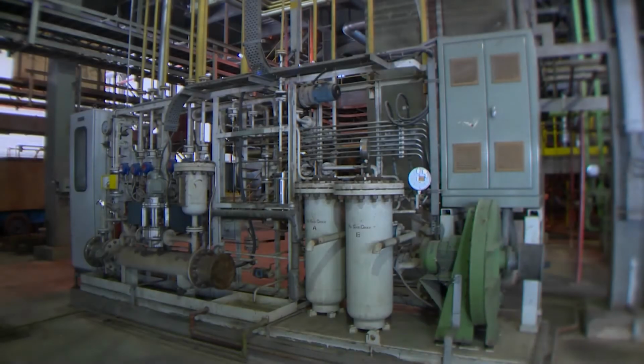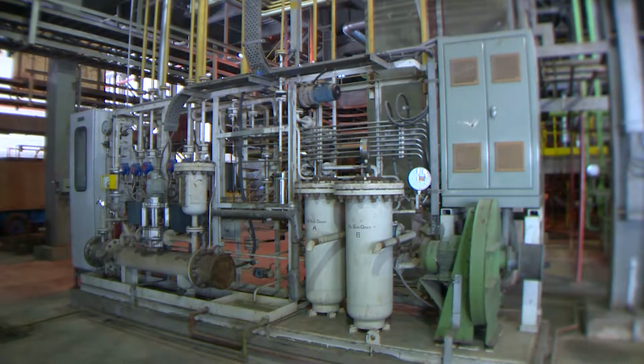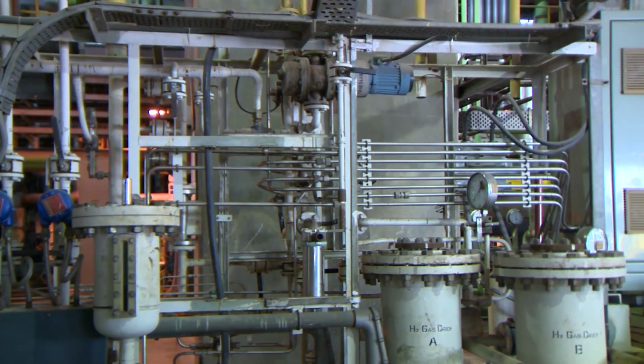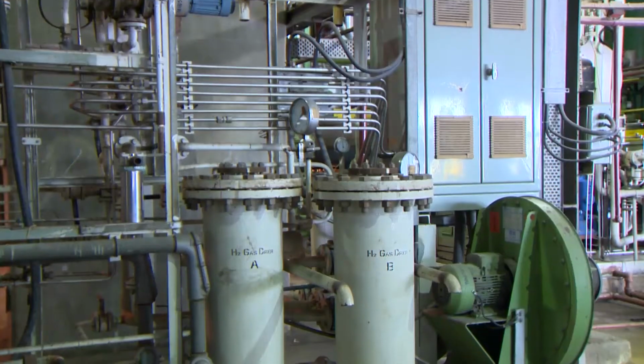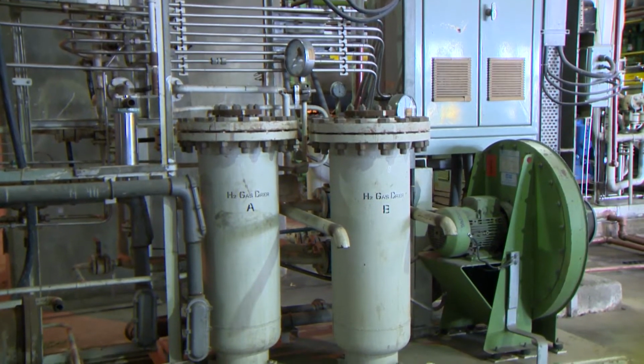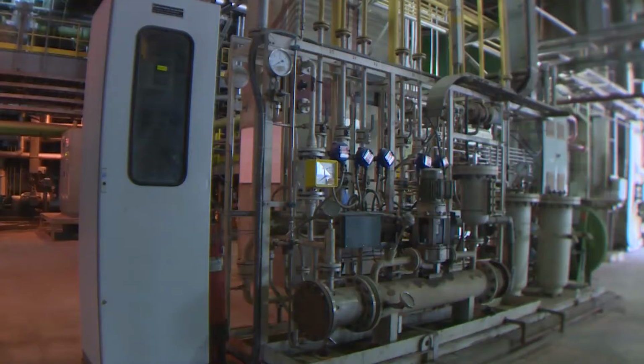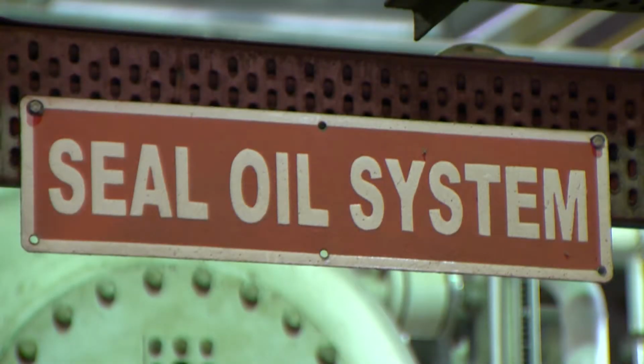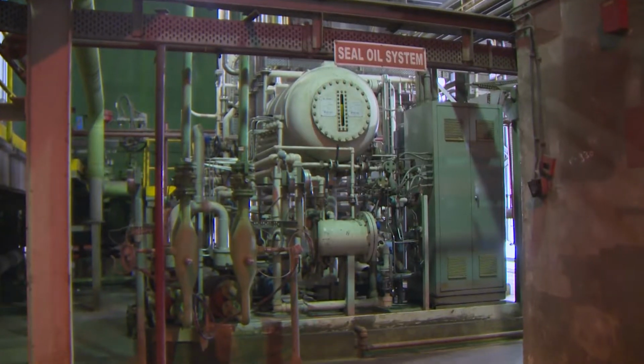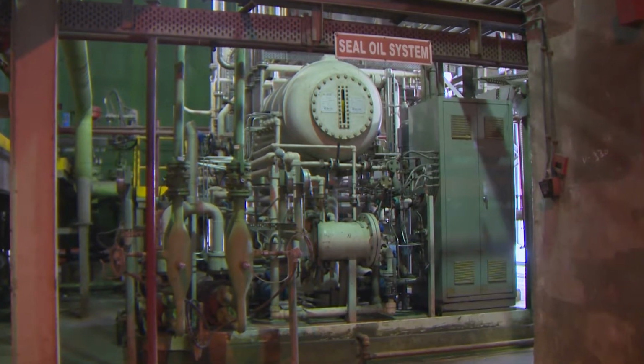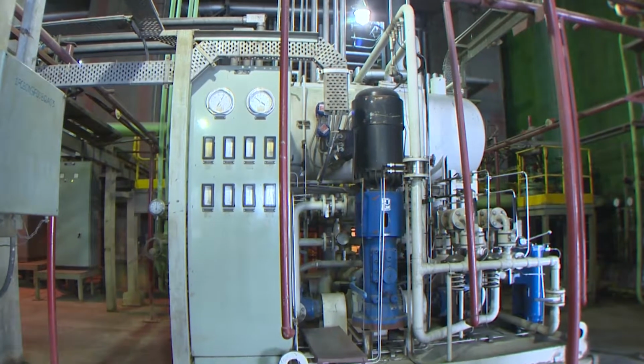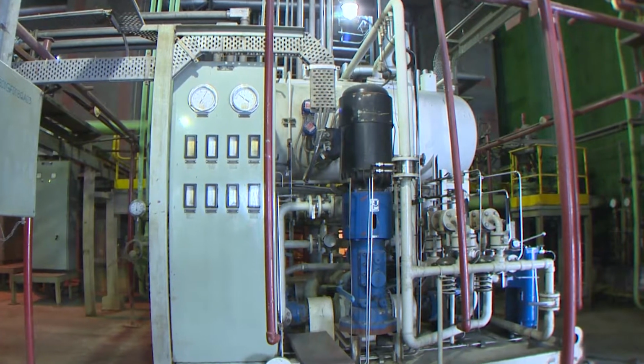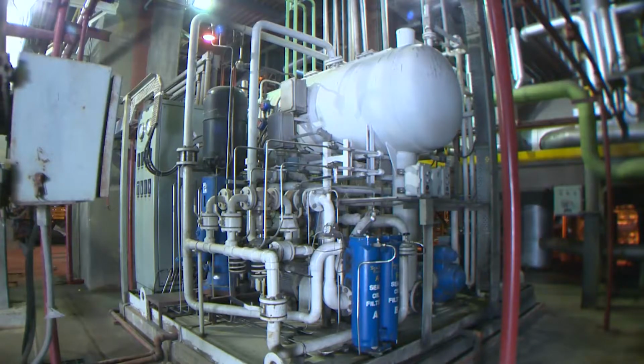Generator auxiliary systems. Hydrogen cooling system. Hydrogen gas is used as a cooling medium in generator because of its less density, high heat transfer coefficient and high thermal conductivity. Seal oil system. In order to prevent the escape of hydrogen from the generator, there is oil in the shaft seal body with seal ring at both ends. The oil pressure is kept higher than the hydrogen pressure.